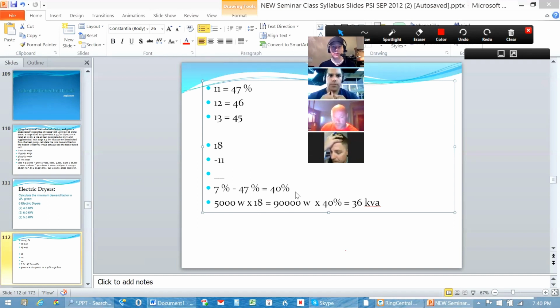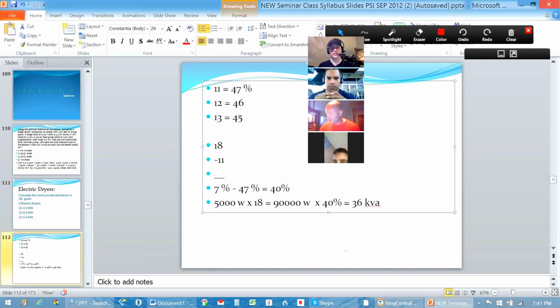Okay, so when you say 18, you're not taking 11 of them, subtracting it from that 18 and doing 47%, and then doing the remainder. You're not doing two different rating steps. That just means anything over 11, you're just using whatever your subtraction is at 1%. It's the whole block of all of them. Yes, that's a good question, because that's been asked many times, but it's not a two-step process. You just adjust your demand factor, and once you adjust it, it applies to the whole group.